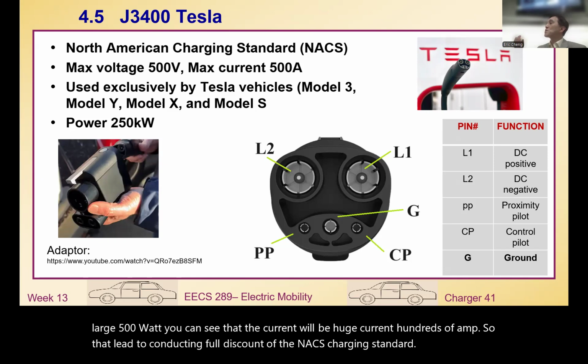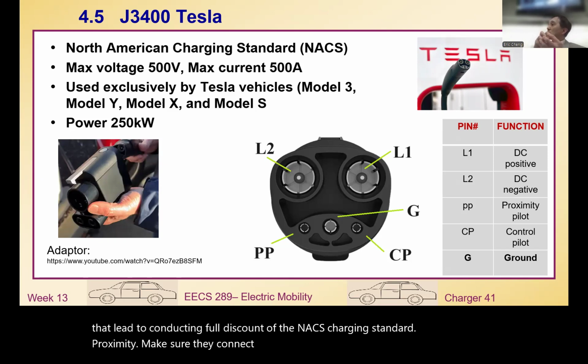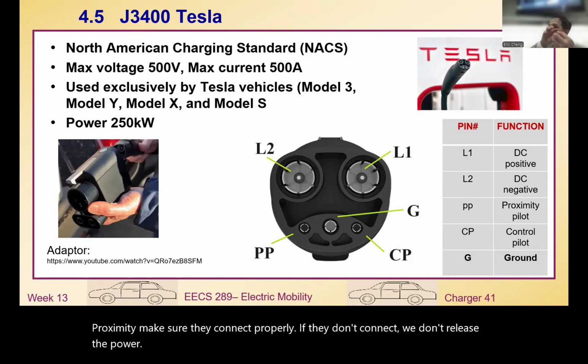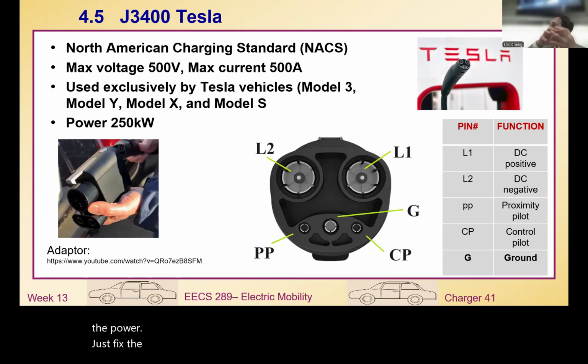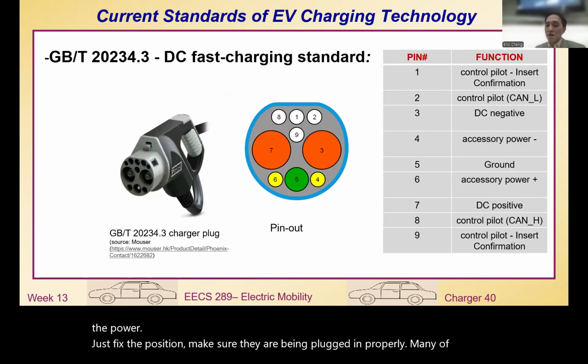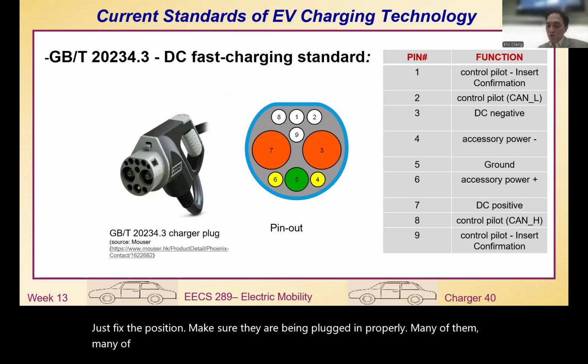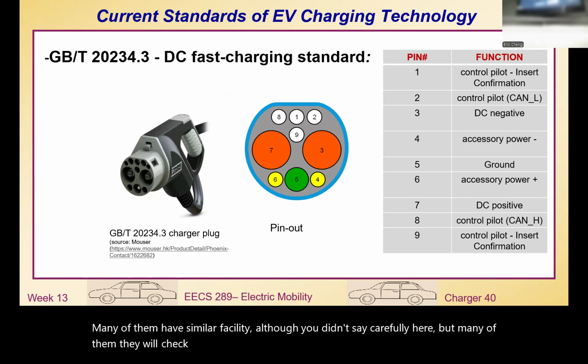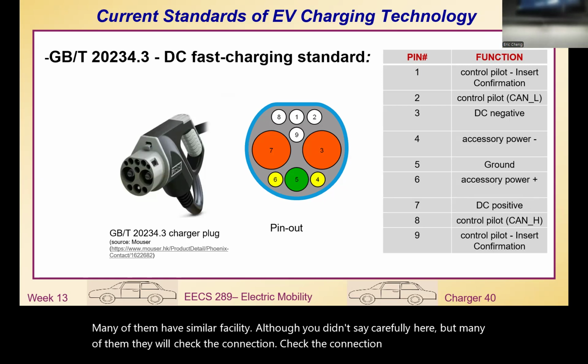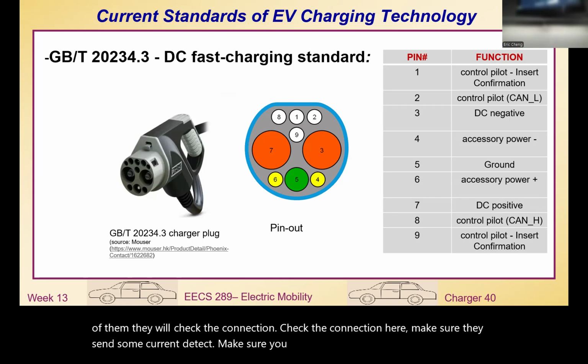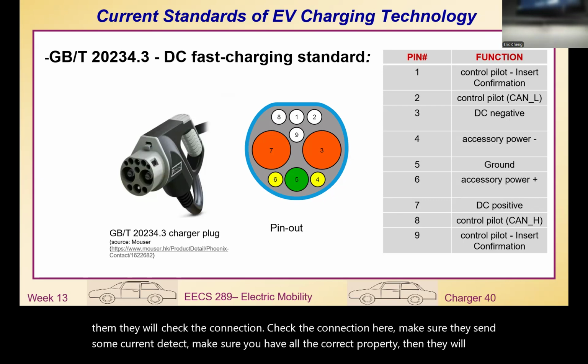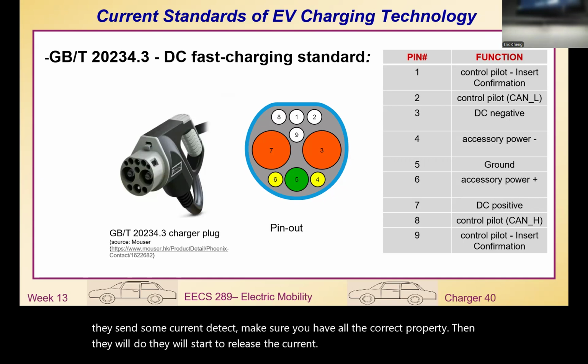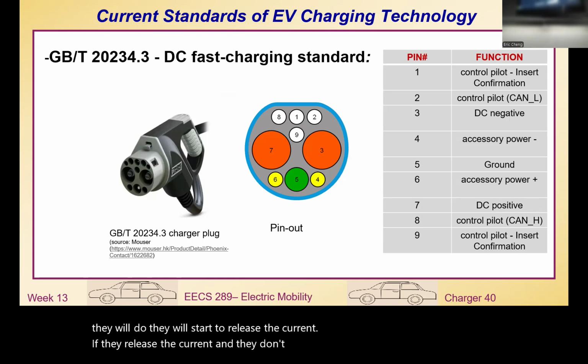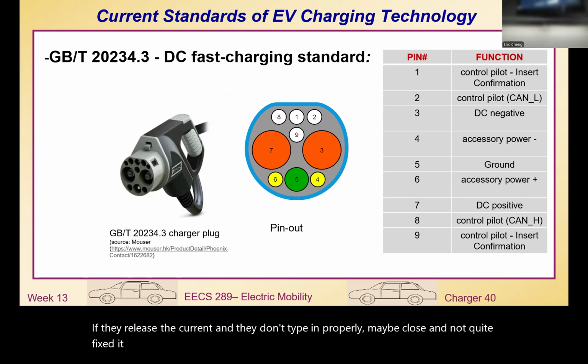The proximity connection makes sure they connect properly - if they don't connect, we don't release the power. It's just a fixed position to make sure they are put in properly. Many connectors have a similar facility, though it's not shown carefully here - many of them will check the connection, send some current to detect that it's already connected properly, then they will start to release the current. If they release the current without it being put in properly, or it's loose and not fixed well, you can create a contact issue.